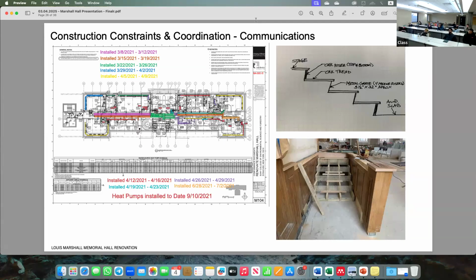So all of a sudden we didn't have the free area needed for that air to be drawn into the plenum. The solution we implemented was building risers with an open area—not really a grill—so that air could be drawn in to make up the free area we'd lost at the front of the stage. But when we turned the unit on, it was drawing so much air it was actually whistling in the auditorium, which is not what you want.